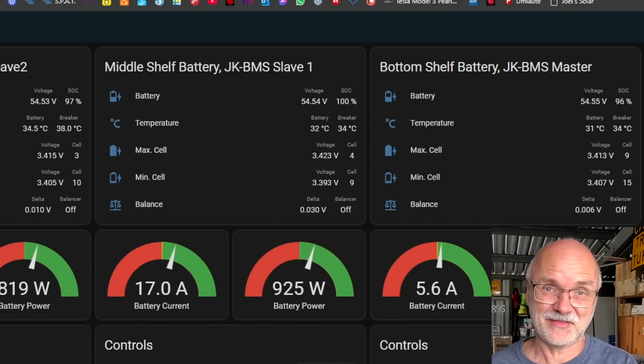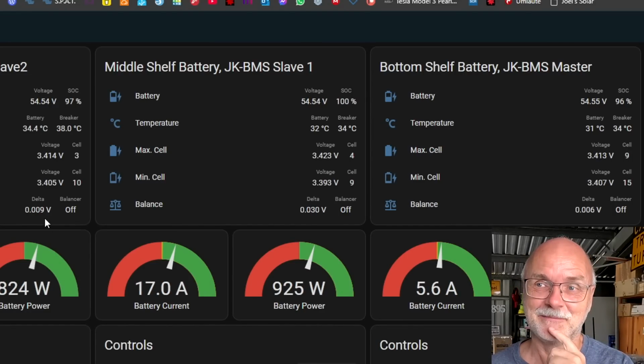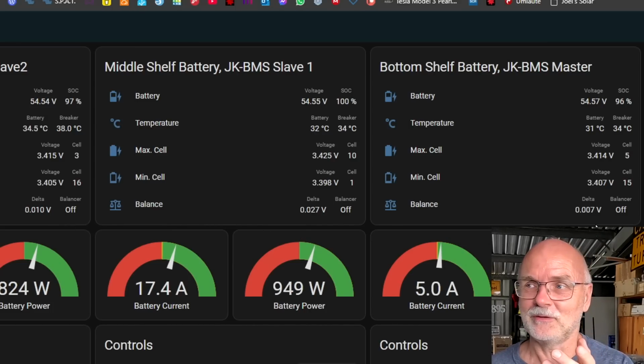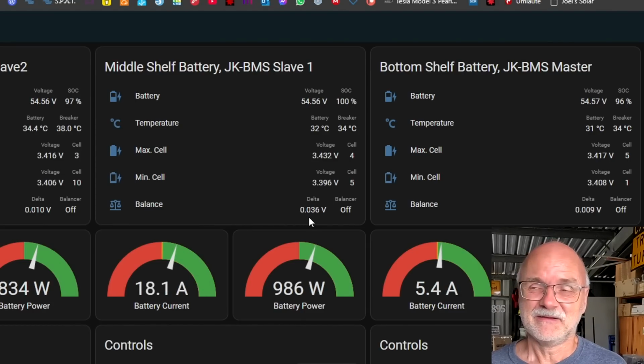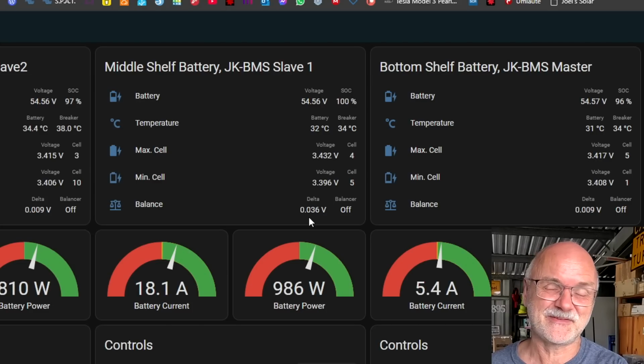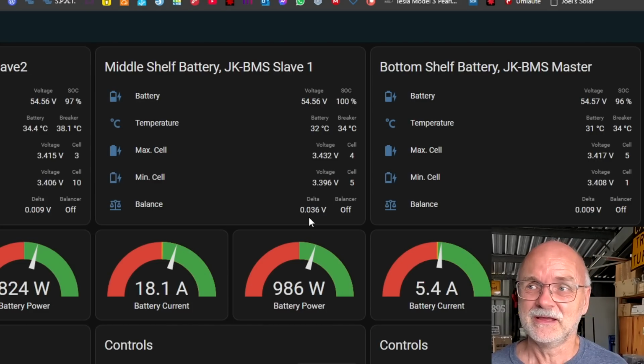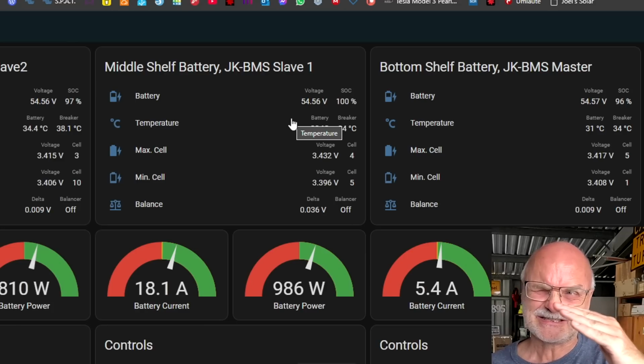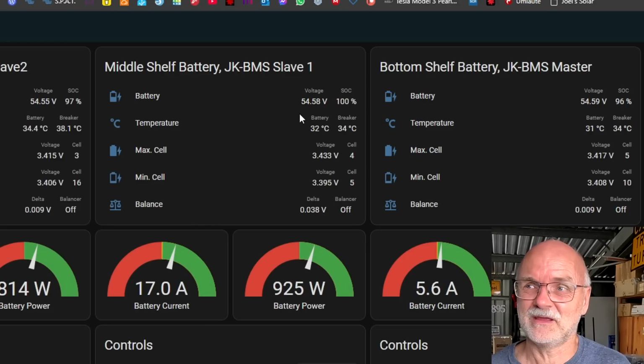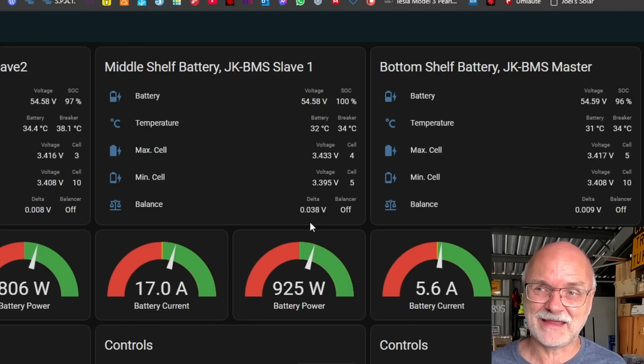Battery testing with solar, and I said before there is a second thing I want to show you - look at the deviation of these batteries. Top battery 9 millivolt, middle shelf 30 millivolt, bottom shelf only 7 millivolt. This one has always the highest deviation as well. At 55.2 volts I sometimes see between 50 and 70, sometimes 80 millivolt of deviation. We are just starting to rise with the voltage here at 54.6 volts now, and you can see the deviation is already a lot higher than with the other batteries.